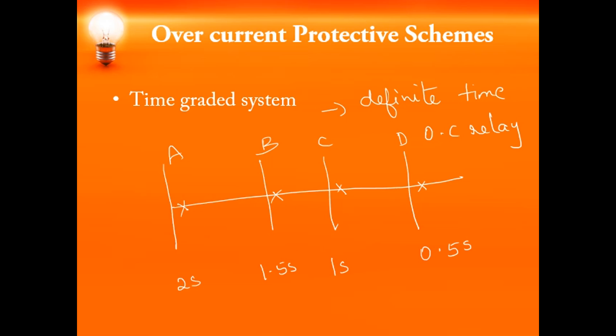Say a fault occurs at a point beyond D. After 0.5 seconds, the circuit breaker at D will operate and the fault is cleared. In case the circuit breaker at D fails to trip, it will wait another 0.5 seconds — meaning only after 1 second will circuit breaker C trip. If B, C, and D all fail to operate, the fault will remain for 2 seconds and circuit breaker A will trip at 2 seconds. So the nearby circuit breaker must detect and trip, else it will cause damage to the entire feeder. There is a disadvantage in this time graded system.